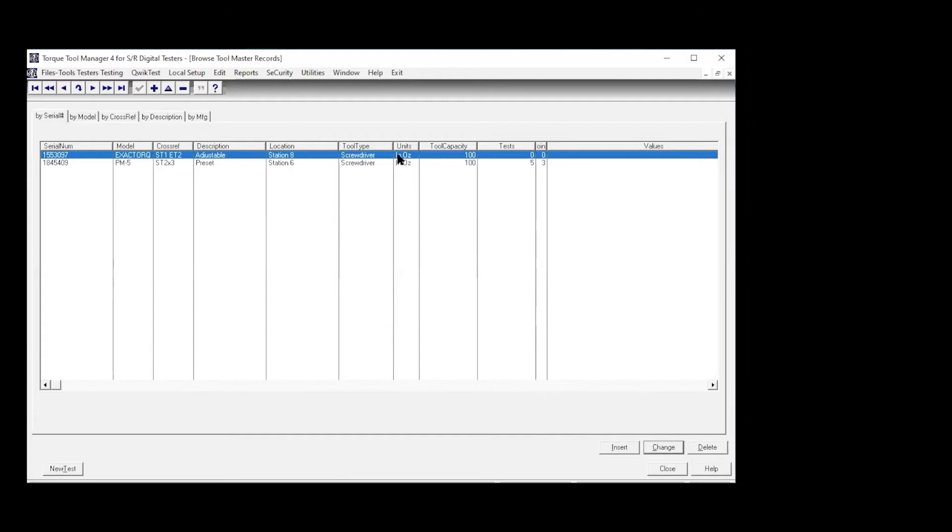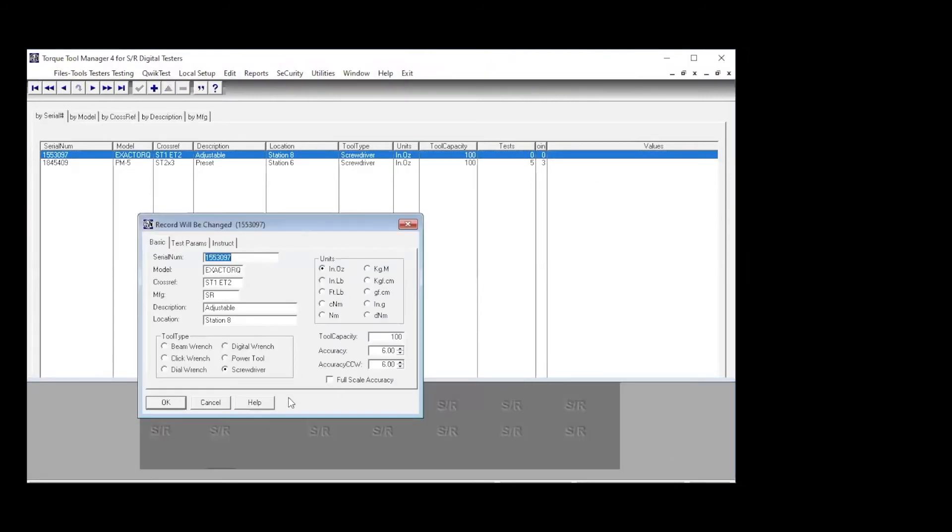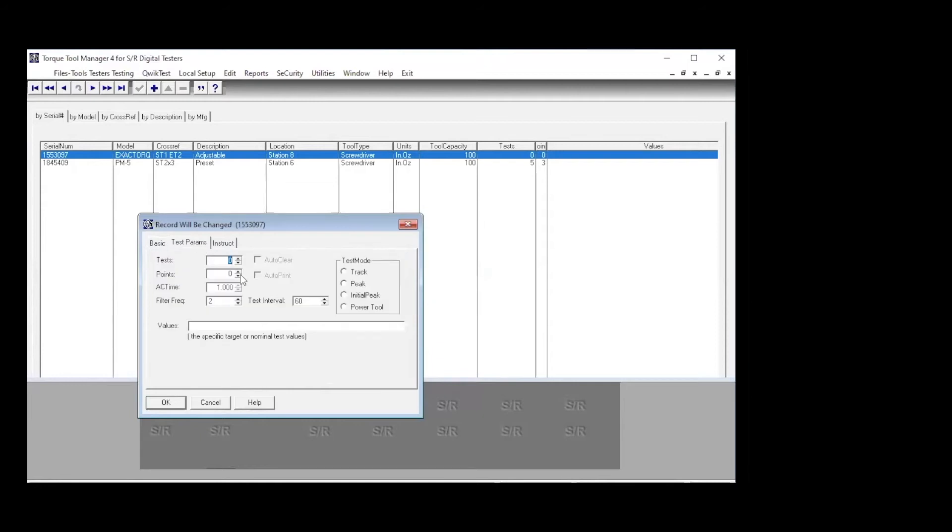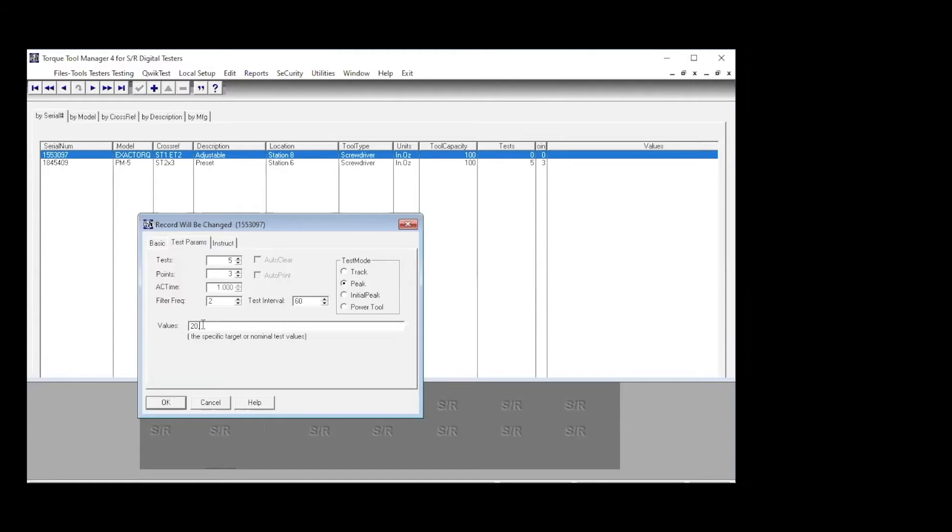But in this one, we don't have the number of tests. And we don't have the values. So we would want to go in and make those changes. And here's a screwdriver. It's an adjustable. Tool capacity, we have all of that. Test parameters. Here we go. We have zero for the number of tests. We want five tests on our torque screwdrivers. And in this particular case, because it's an adjustable, we want to test at three points. And we want to use peak mode for testing screws. Target is nominal. Test values, the specific target. These are the values where we're going to test this. We're going to test it at 20% comma, 60 comma, and at 100. And since this is inch ounces, we're going to test this at 20 inch ounces, 60 inch ounces, and 100 inch ounces. We're good. We can close. Okay. Now that we've done that, close out of here.